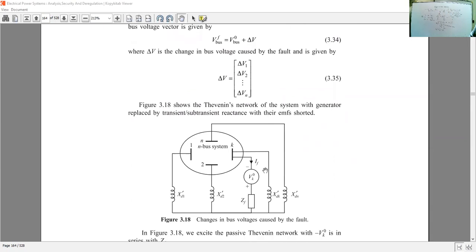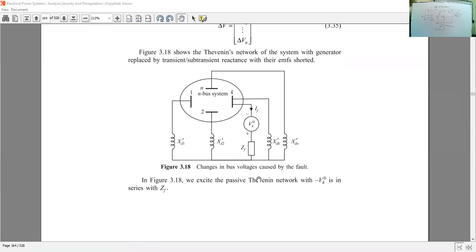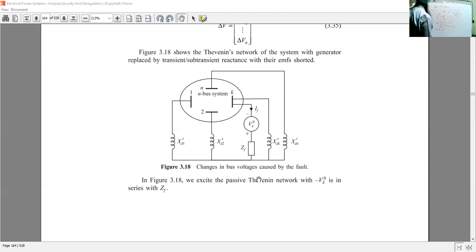We apply the Thevenin equivalent representation. For the Thevenin equivalent representation, all generators are short-circuited and replaced by their transient or sub-transient reactances. K is the bus where the fault has occurred. The Thevenin voltage is applied at the kth bus in series with the fault impedance Z_F such that the fault can close from the kth bus towards the ground. This is shown in figure 3.18, which gives the passive Thevenin impedance network.